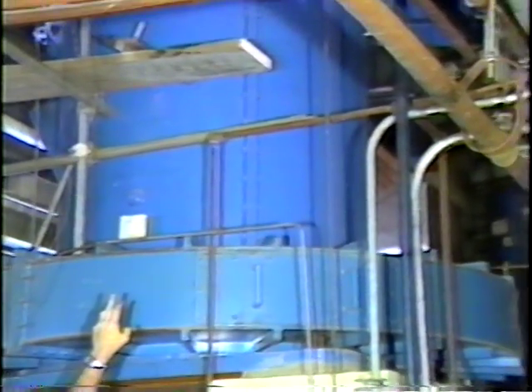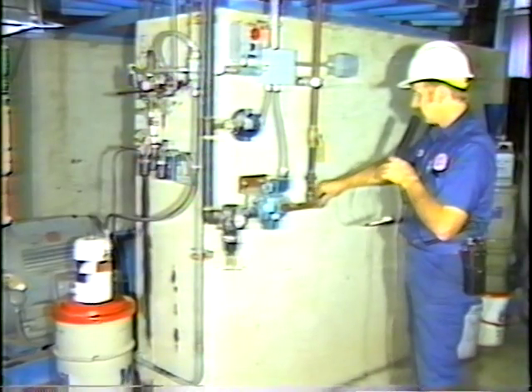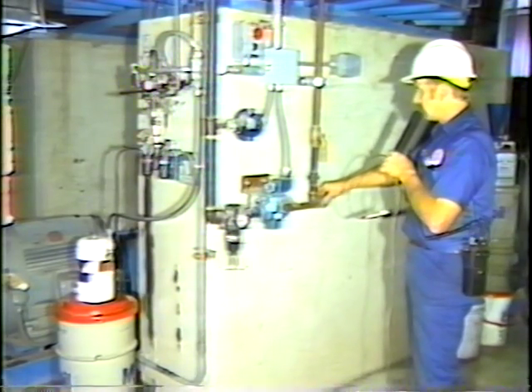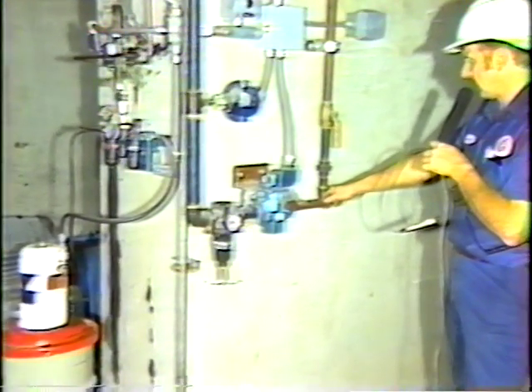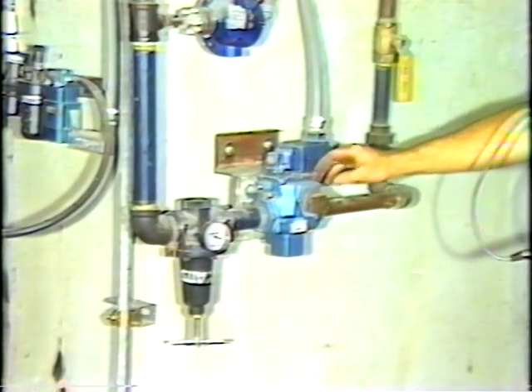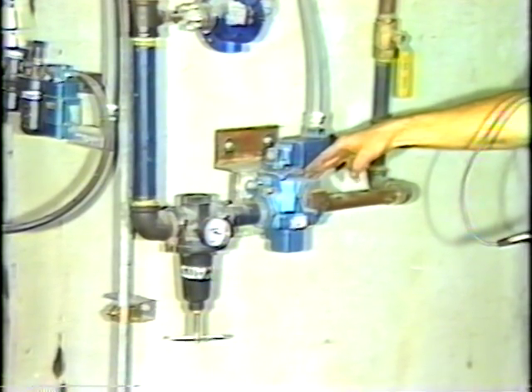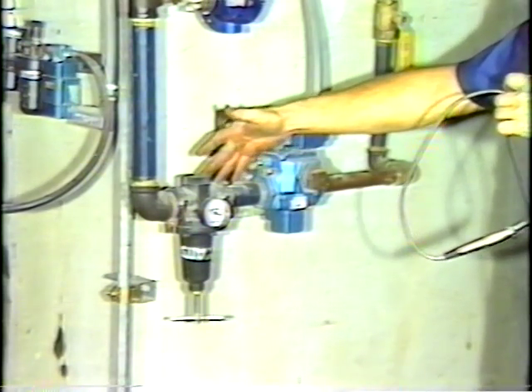into the interior of the mill through the air seal chamber. This is where the air seal assembly begins. This is a plant air supply coming to us. We have to have a minimum of 15 pounds per square inch. It goes through a solenoid valve, which is controlled by the Williams computer, leaves there, and goes on over to a pressure regulator.